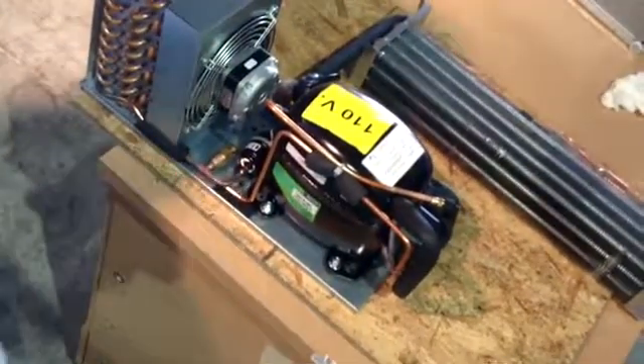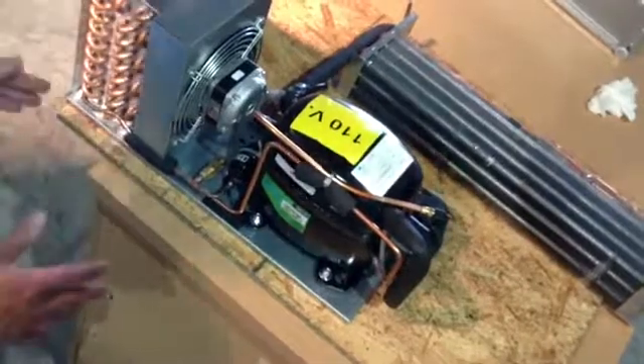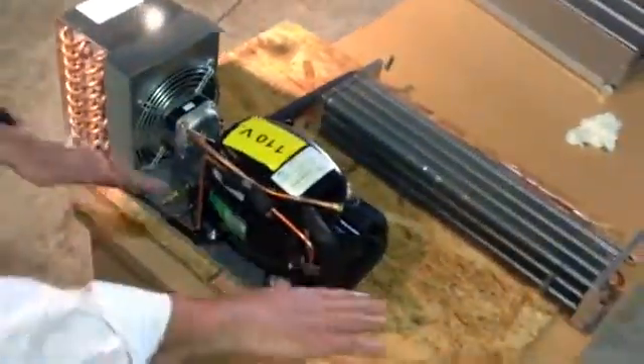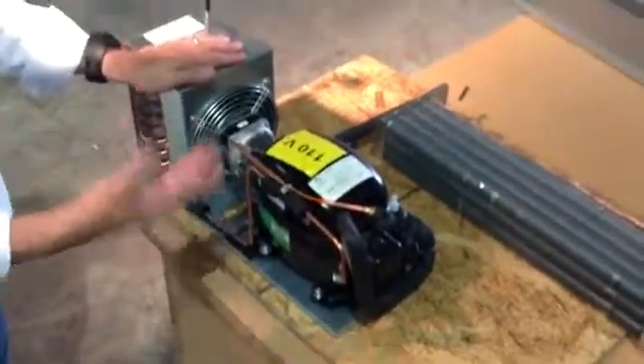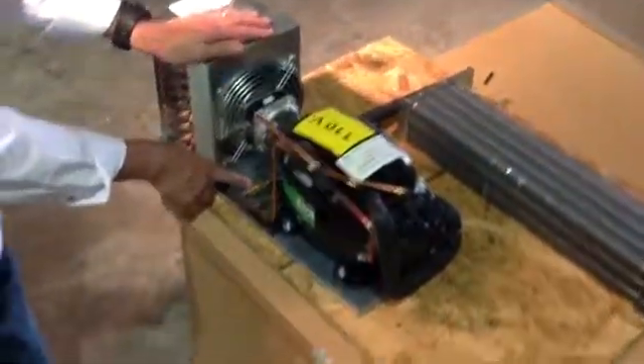Common things that go wrong with your cooling unit: if we don't have the proper spacing between the back of the machine and the wall to let the warm air cool out, the warm air is going to stay circulating inside of this cooling unit area. If the temperature reaches a certain point, it's going to blow this fusible plug.